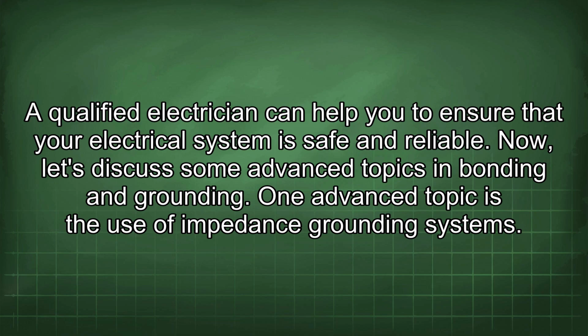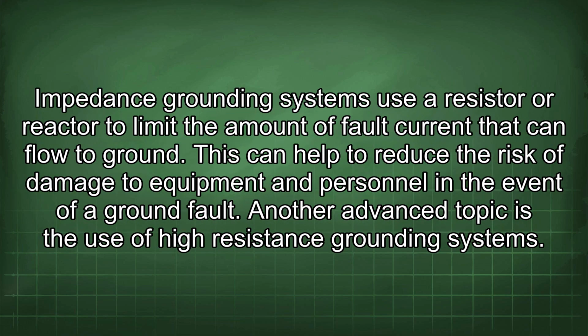One advanced topic is the use of impedance grounding systems. Impedance grounding systems use a resistor or reactor to limit the amount of fault current that can flow to ground. This can help to reduce the risk of damage to equipment and personnel in the event of a ground fault.